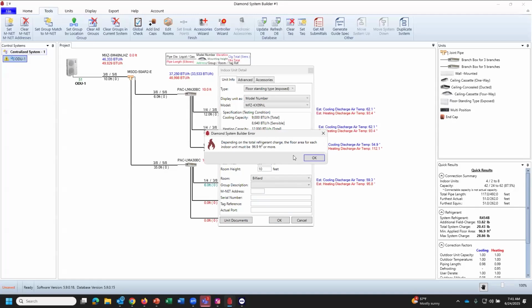a 454B system, this room does not have enough floor area. We need that floor area to be 96.9 square feet. I'm not going to get into a whole lot of the 454B updates, this is more to show you what happens and how this catches those. But that indoor unit, the floor area must be 96.9 feet, so this room is a hair small. Undercutting the door, putting a louver in a door so that you've got proper conditioned space, can actually allow you to overdo that and include those rooms onto the square footage.